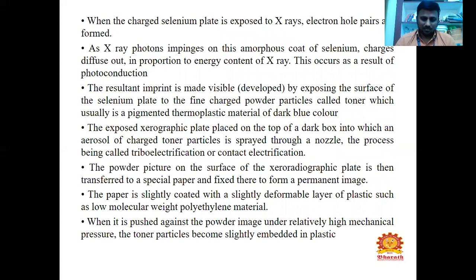When the charged selenium plate is exposed to X-rays, electron-hole pairs are formed. As X-ray photons are absorbed in the selenium, charges diffuse out, recording the information energy content of the X-ray. They occur as a result of photoconduction. The resultant latent image is made visible by exposing the surface of the selenium plate to fine charged powder particles called toner, which is usually a plastic material, dark blue in color.